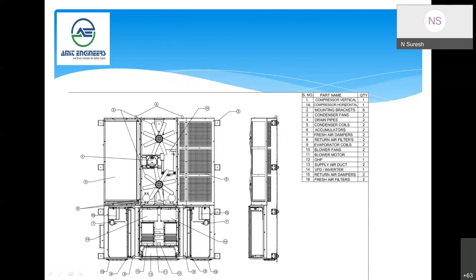And there are two axial condenser fans, which, as briefed, take in air from this area and exhaust it here for condensing application. And there are drain pipes. Two drain pipes are available at the rear of the unit, which are routed from the evaporator drip tray, where whenever there is a temperature difference, condensation happens. The water collected from the drip tray is taken through this pipe and connected to an external drain pipe, and there is a provision available on the coach where the drain will be dropped, so that there won't be any spilling over the coach.